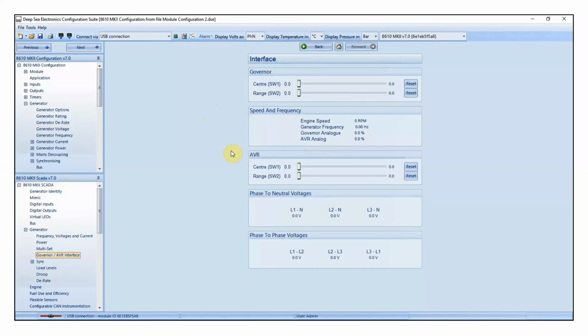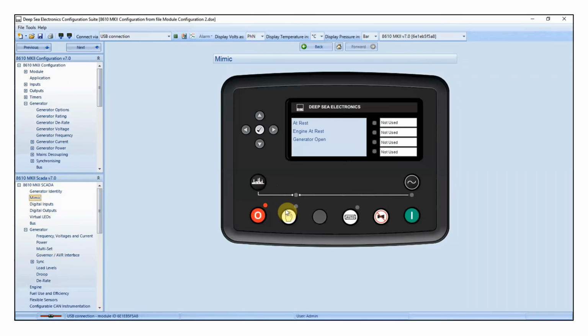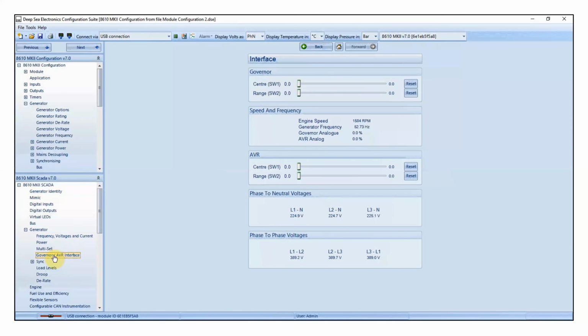So the first thing we're going to be doing is actually setting switch 1 of the governor. The way we do that, we start the generator, and it's very important you leave the generator breaker open. As you can see here, it's not being requested to close. We then go to the switch 1 slider of the governor, and we start to adjust. By default, the values will be at 0, and all you need to do is keep increasing that switch 1 value until you attain whatever your nominal frequency is. In this example, 50 Hertz.